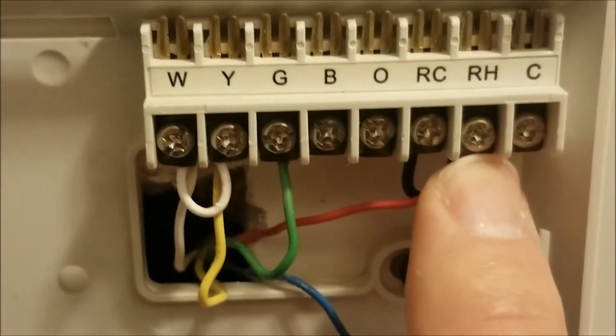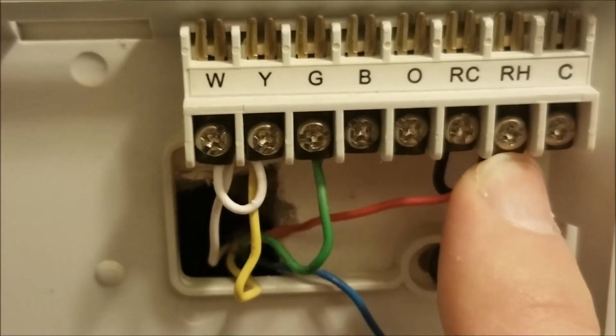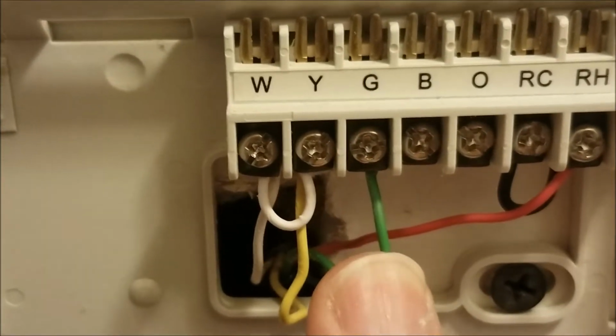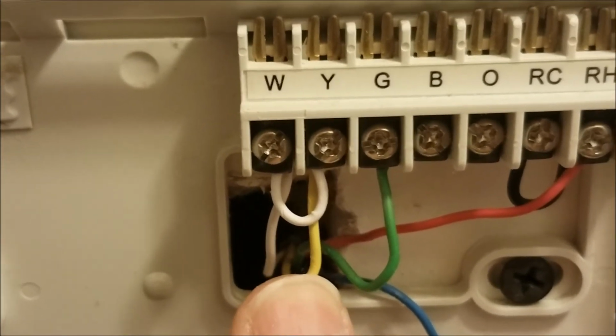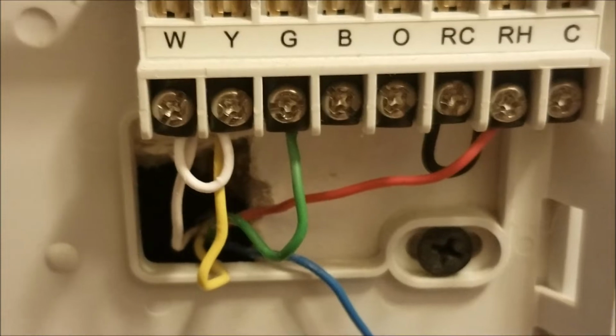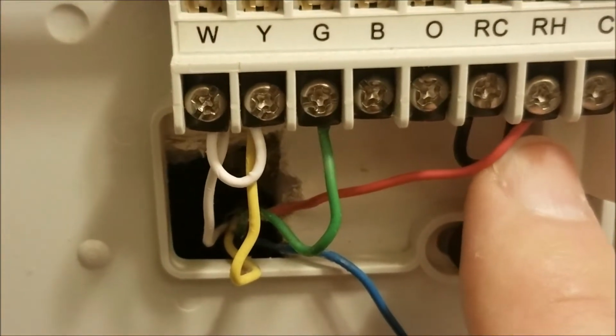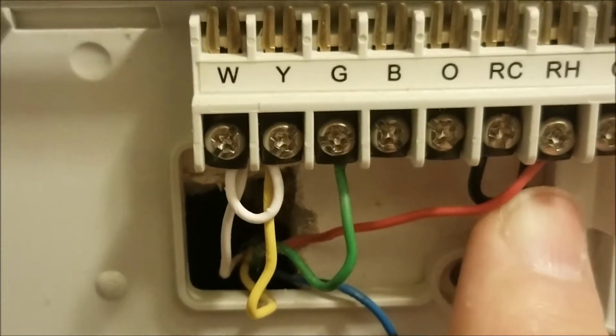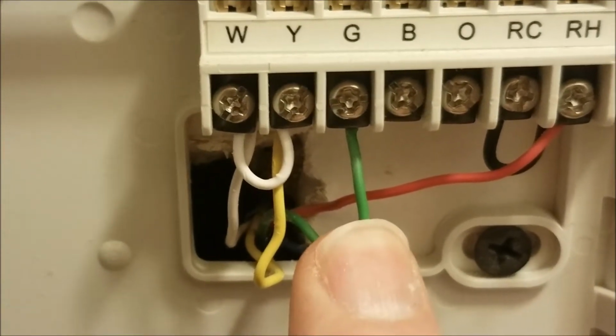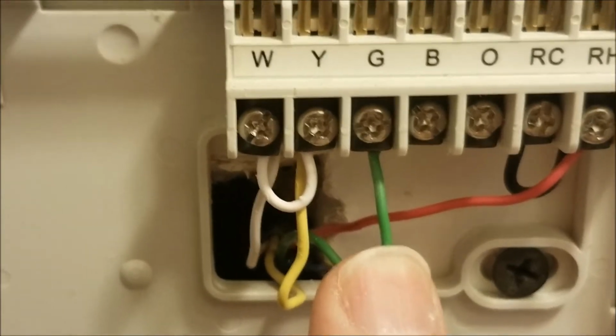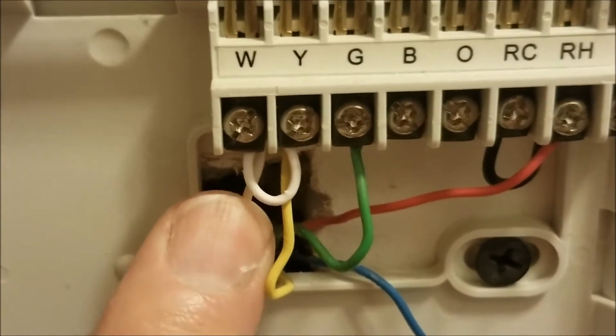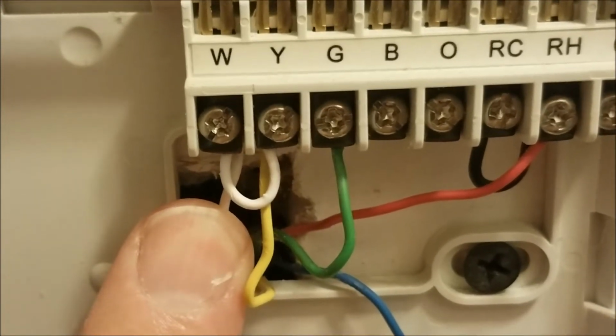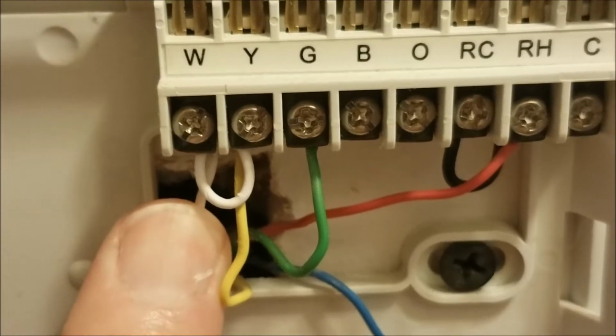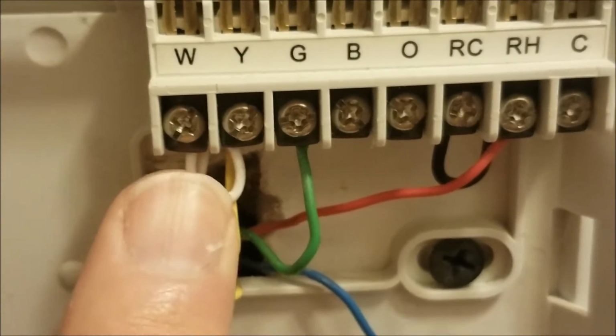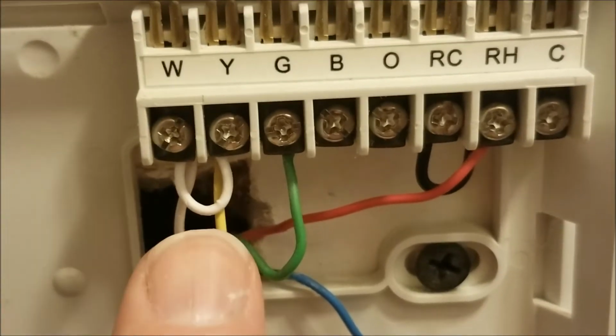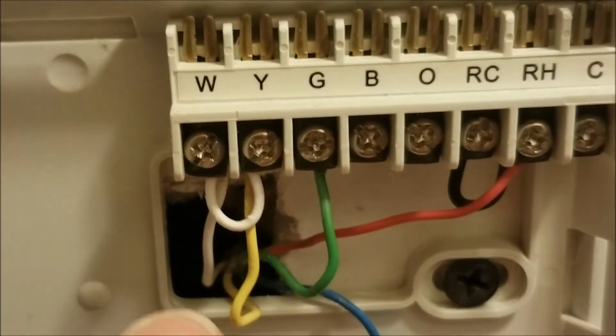So in this case, when I'm in cooling mode, the same thing works. It takes this 24 volts and connects it to both the fan and the compressor, right? But the way my thermostat's set up, it's a little bit older, I don't know, 15 years old. It takes the red wire, that 24 volts or 26 volts, whatever it is, and then turns the fan on, as well as the heat. Well, the heat doesn't go to anything. So this doesn't have an auxiliary for a heat strip. So basically the heat now has to also turn on the compressor, which is this yellow wire.